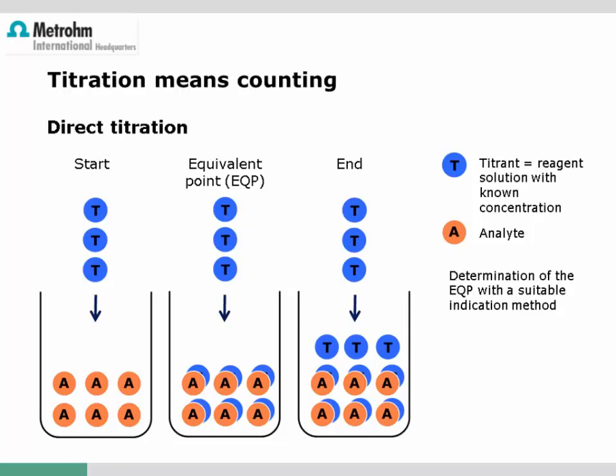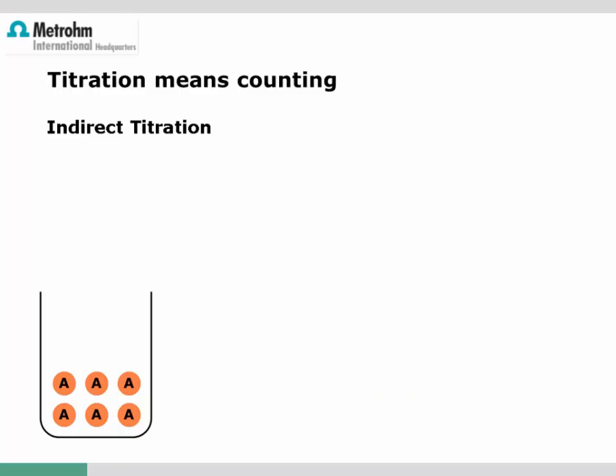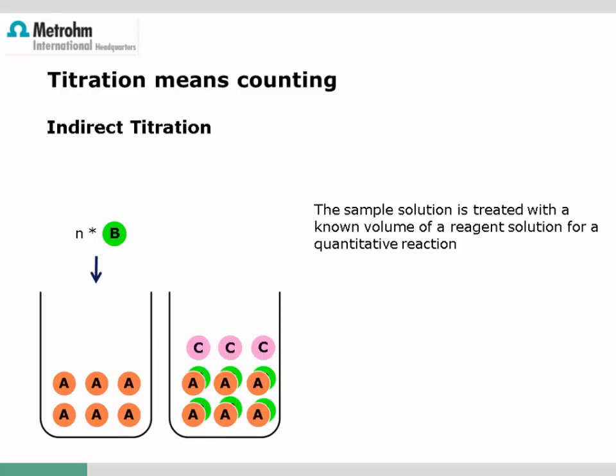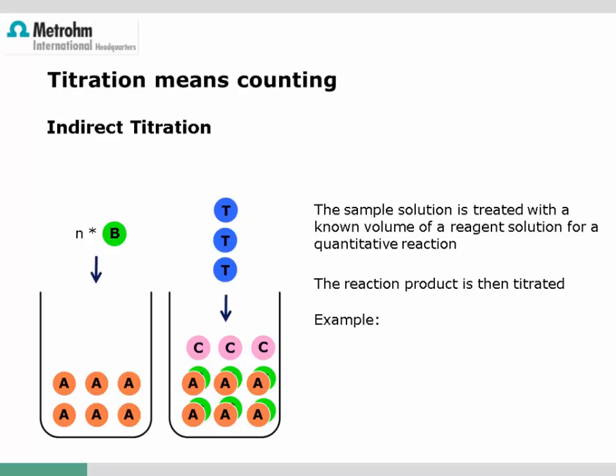Not for every analyte can a direct titration method be used — for example, if no suitable sensor is available. In this case, a so-called indirect titration method is used. For an indirect titration, a known amount of reagent solution is added to the sample solution. This reagent reacts with the analyte and a new species is formed, and by titrating this new species we can calculate the original amount of the analyte in the sample.